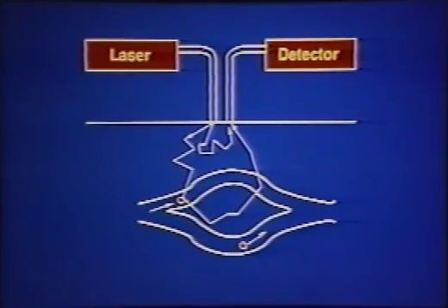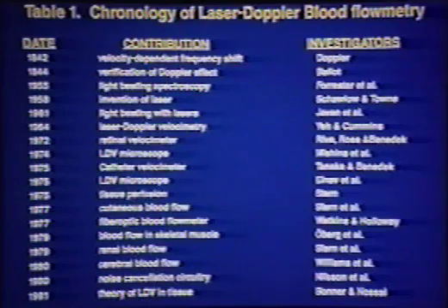And then our main interest in today's presentation, though, is the measurement of blood flow in tissue, in a small volume of tissue in which the only blood vessels present are of microscopic dimensions. And in this case, we deliver laser light to the tissue where it's diffusely scattered. Much of the light that returns to the detector by way of the receiving fiber has interacted only with static tissue elements, but a small fraction of it has interacted with moving red blood cells and thereby experienced a frequency shift. So these two types of light would be captured by the receiving fiber and carried back to the detector.